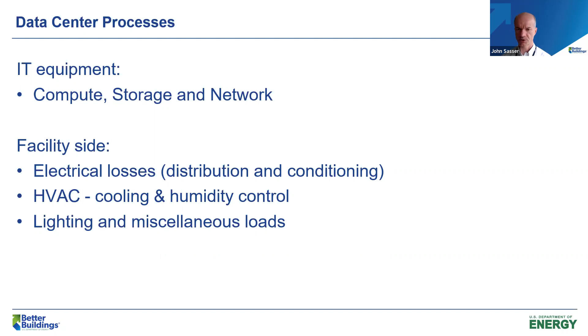By definition, PUE is the total energy used in the building divided by the IT energy. In this pie chart, dark blue is the IT equipment, which by definition is one. The next largest category is typically the cooling equipment, the HVAC, which in this 1.56 PUE data center, fairly typical across the industry, is probably 0.5. So about a third of the total energy is HVAC and about two-thirds is IT equipment. Electrical losses are the next largest category, largely in the UPS, but still fairly small.